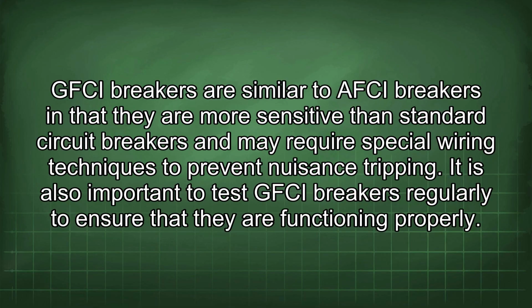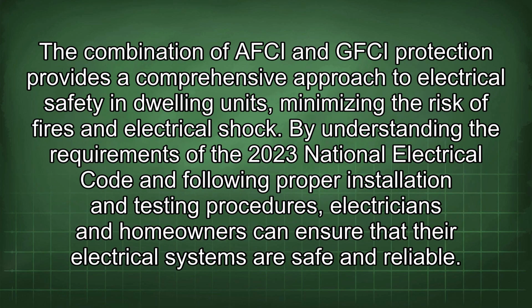GFCI breakers are similar to AFCI breakers in that they are more sensitive than standard circuit breakers and may require special wiring techniques to prevent nuisance tripping. It is also important to test GFCI breakers regularly to ensure that they are functioning properly. The combination of AFCI and GFCI protection provides a comprehensive approach to electrical safety in dwelling units, minimizing the risk of fires and electrical shock. By understanding the requirements of the 2023 National Electrical Code and following proper installation and testing procedures, electricians and homeowners can ensure that their electrical systems are safe and reliable.